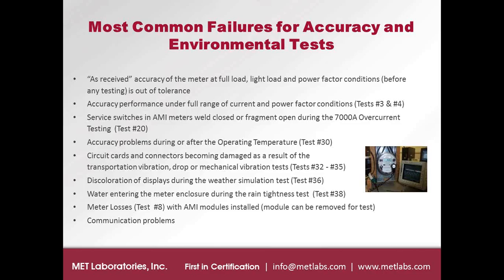Discoloration or fading of the displays or external parts of the meter during the weather simulation test. We see that occasionally. The water ingress, not too often, but every once in a while we'll see the water test fail, that rain tightness test. Meter losses, we'll see that be out of tolerance, typically with the communication module, say on one meter internal, although those modules are allowed to be removed to make that measurement, but we'll still note that needed to happen in order to be compliant with that particular test.